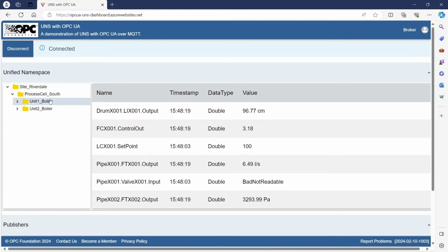The data streams are designed to be very small, only containing the changes from the last update. The metadata tends to be larger, and has descriptive information such as human-readable text. Every data message can be linked back to the associated metadata. Data messages can also have a metadata version, which signals to the subscriber that their metadata may be out of date. The metadata itself is sent to a different topic that has the retain flag set.